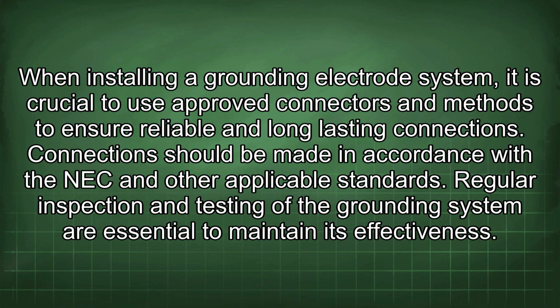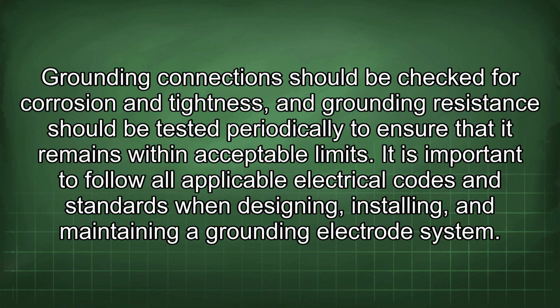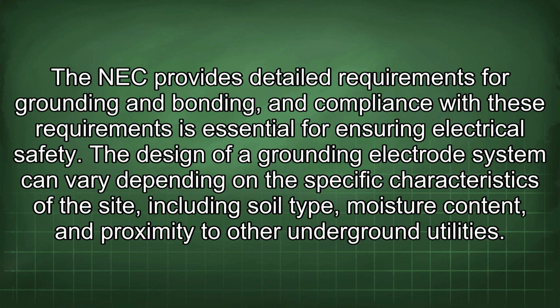Regular inspection and testing of the grounding system are essential to maintain its effectiveness. Grounding connections should be checked for corrosion and tightness, and grounding resistance should be tested periodically to ensure that it remains within acceptable limits. It is important to follow all applicable electrical codes and standards when designing, installing, and maintaining a grounding electrode system. The NEC provides detailed requirements for grounding and bonding, and compliance with these requirements is essential for ensuring electrical safety. The design of a grounding electrode system can vary depending on the specific characteristics of the site, including soil type, moisture content, and proximity to other underground utilities.